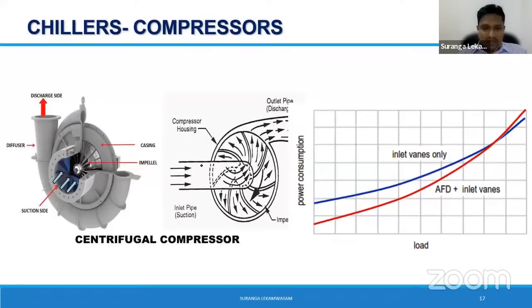That has some negatives also, because you may have heard of chiller surging, which happens in centrifugal chillers. That is because this is a centrifugal machine. They are very efficient. You can find them at very big capacities, about 500 ton and above. The uniqueness of the centrifugal chiller is that it gives good efficiency closer to 100% load, probably above 80%. They are very good in full-load efficiency, not so good in part-load efficiencies, whereas scroll and screw are much better in part-load efficiency. So when you select the machines, you have to think about all these parameters.